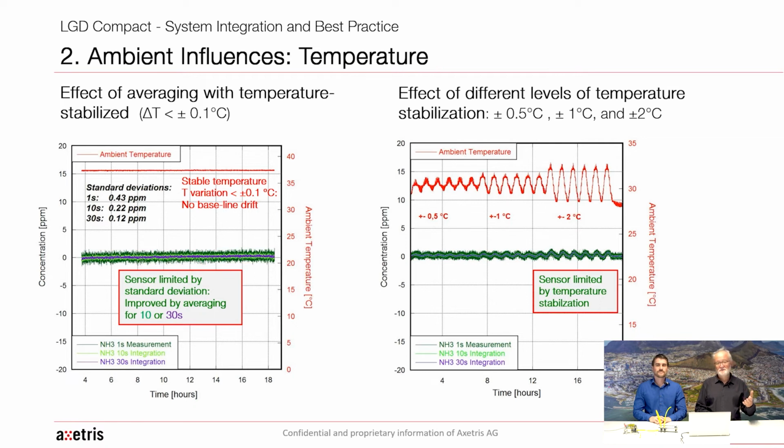When you are at 0.5 C, the fast noise you always have is still dominant. But when you go to 2 degrees C modulation of the ambient temperature around the unit, this modulation caused by the temperature-varied étalon is much bigger than the noise.